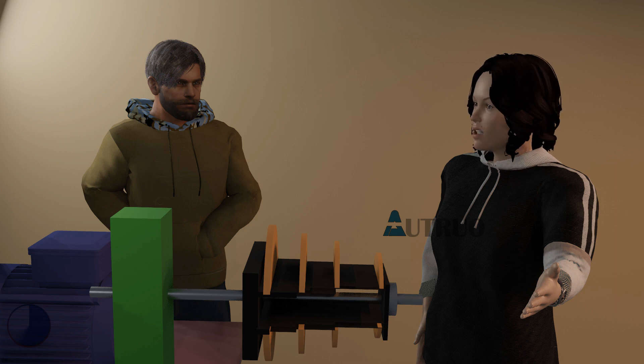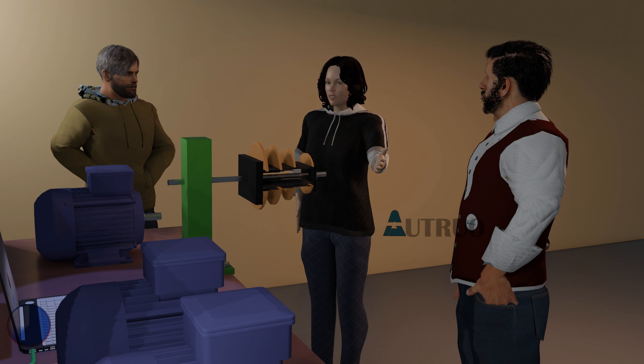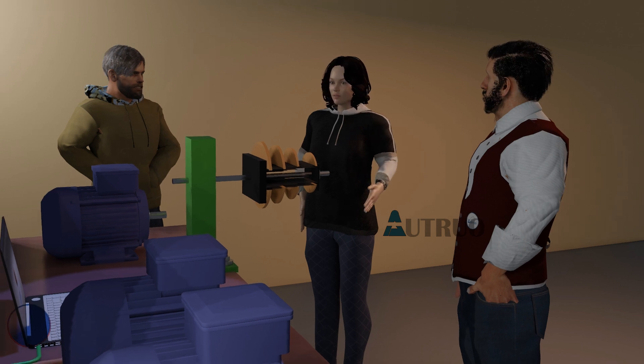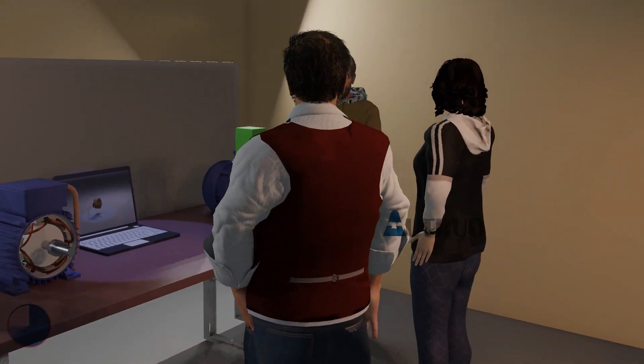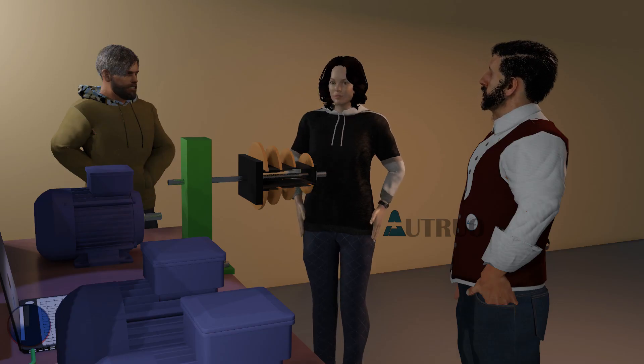Looking at the distributed winding waveform, the rotor starts from rest and the gradual rise of the slope depicts the rotor movement cutting across the air gap until it reaches the midpoint between the two or more wound teeth, after which it gradually drops off exponentially. A motor with a trapezoidal waveform will deliver a greater deal of torque compared to a motor with distributed windings.